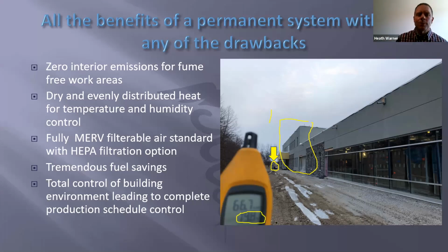So zero emissions inside the work area, dry and even heat because all the combustion is outside. It actually causes evaporation, and it's fully MERV filterable. And here's the kicker: you can actually adapt these to use HEPA filtration too. So now not only are you taking care of dust particulates on a job site, you can add a HEPA filter option and take care of all viral particles. Tremendous fuel savings. Instead of costing you more money to operate like a permanent HVAC system, this system will actually pay you to use itself. So as far as health and safety, top of the list. In fact, what you essentially have is a permanent HVAC system on a temporary basis that was designed specifically for construction, all saving the wear and tear on your permanent system.